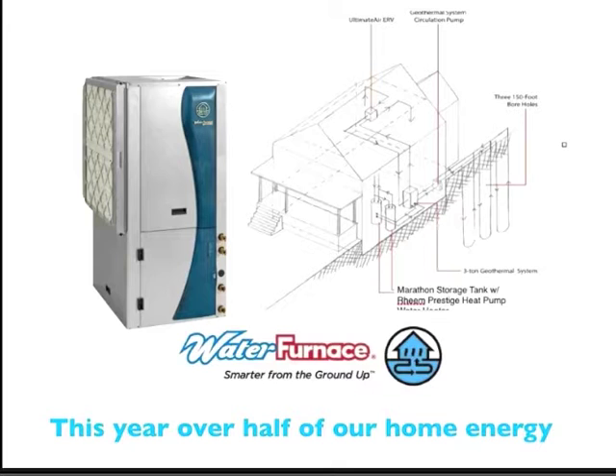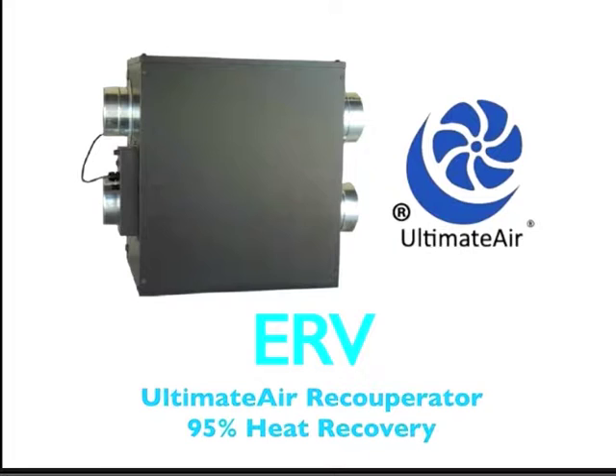The water tanks, we went from standard electric resistance water tanks for storage for the geothermal de-superheater and our hot water. And when we upgraded those, we saw a reduction in kilowatts of 50% by putting in a heat pump water heater. And I do want to note, the heat pump water heater in a climate like ours is awesome in the summertime.